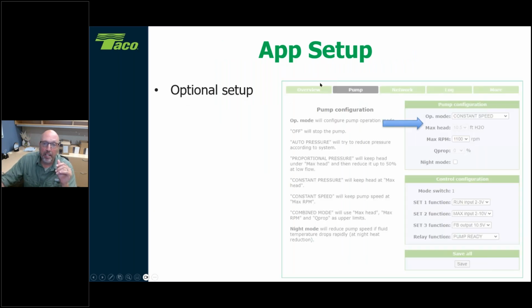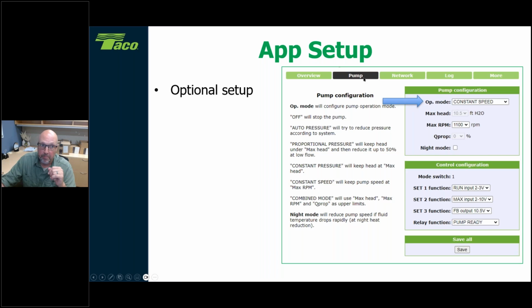Now, you want to do some settings. We click on the pump tab, and now you can program this circulator from here instead of the faceplate. So yes, you can do the settings from the faceplate and go through the buttons themselves, or you can do it from here, your choice. Same thing, does both. I still suggest if you program via the faceplate, log in and take some screenshots, so you capture how you left the circulator, rather than taking pictures on your cell phone and then coming back to it 3 years later and scrolling through your phone saying, I'm going to get there, it's here somewhere. At least with a screenshot, you put it in the file and you're good to go.